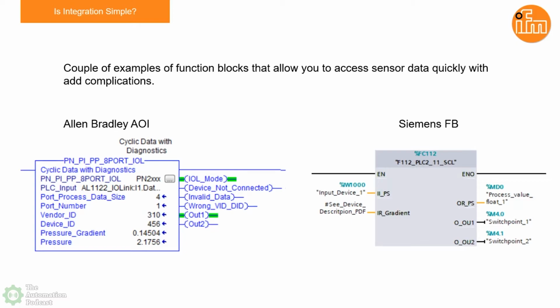So in this case, I'm showing you two function blocks that IFM has developed for the Allen Bradley systems and Siemens systems. What they essentially do is you drag and drop these into your logic, plug in your sensor, fill in a couple parameters. For example, with the Allen Bradley AOI, you give the AOI a name, tell it which input data array to use - usually just the input data array of the IOLink master block you're trying to use - and then what port number the sensor is connected to. You fill in those three parameters, and we give you the rest of the data, including the vendor ID, device ID, the pressure value, and all the diagnostic information.